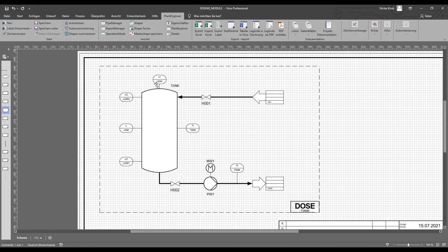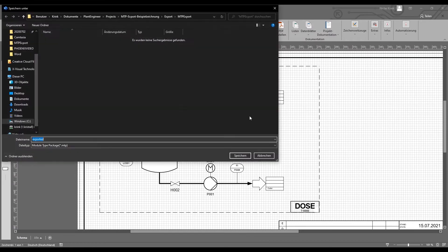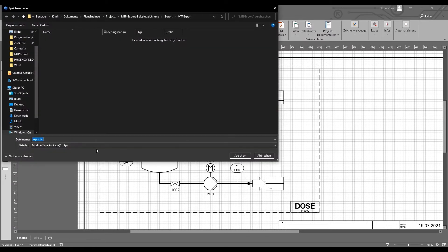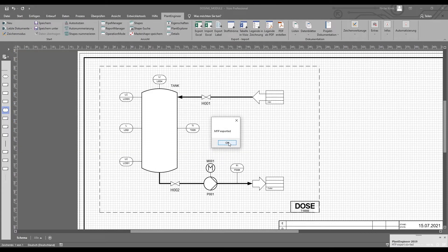This means that for each icon on the P&ID, I can define whether it should appear on the MTP operator display and to what extent it should be able to be measured and controlled by the MTP. The limits of my operator display are defined by the dashed module frame. I can easily initiate the export of the MTP via the user interface: I assign it a name, click save, and the MTP is exported after just a few seconds. The resulting MTP can now be imported into an environment for engineering the module.